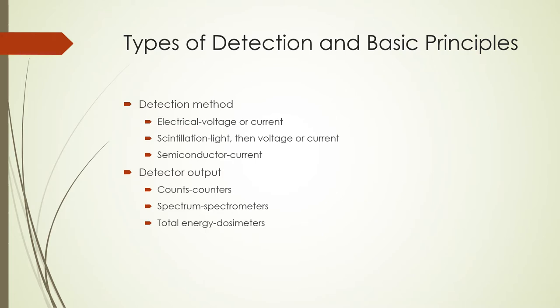Radiation detectors can be classified based on their detection method or the detection output. Electrical detection involves converting the radiation to either voltage or current. When a scintillator is used, the radiation is converted first to light, then to voltage or current. Semiconductor detectors usually convert radiation signals to current. At the output of the detector, the signal can be displayed in several ways. Detectors displaying counts are called counters, those displaying a spectrum are called spectrometers, and those displaying total energy are called dosimeters.